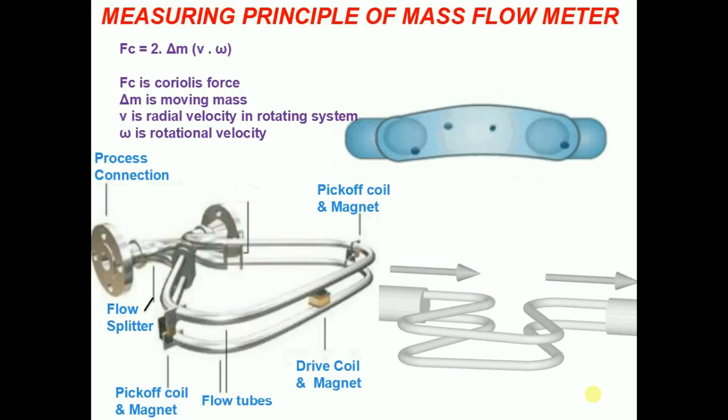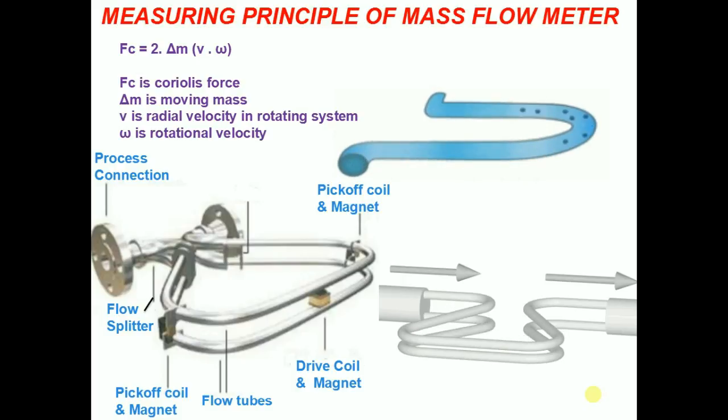The time difference between the sine waves is measured and is called delta T, which is directly proportional to the mass flow rate.